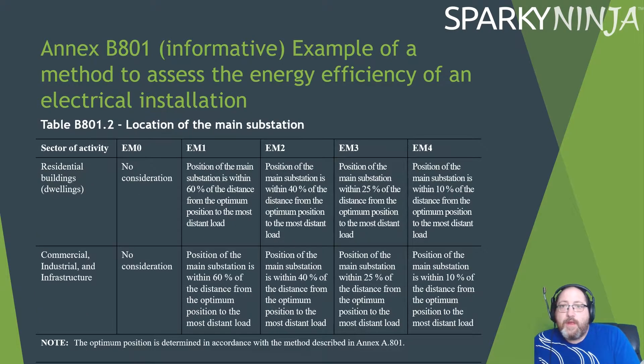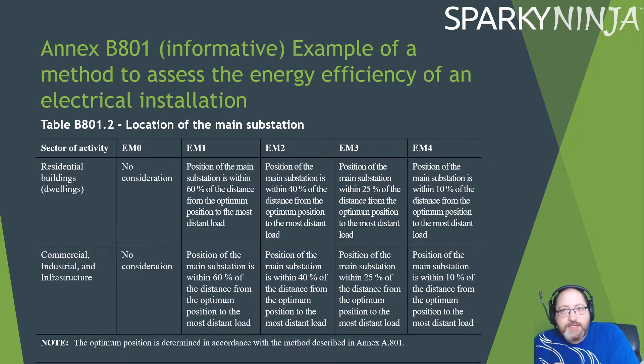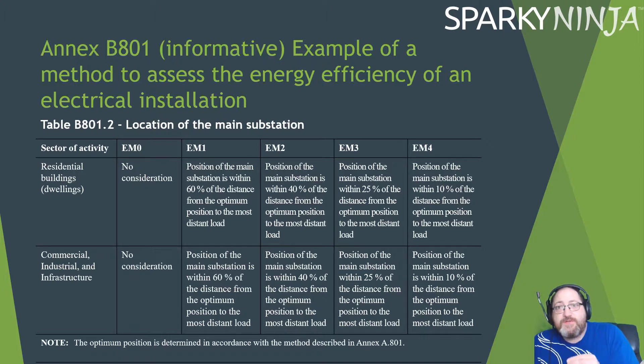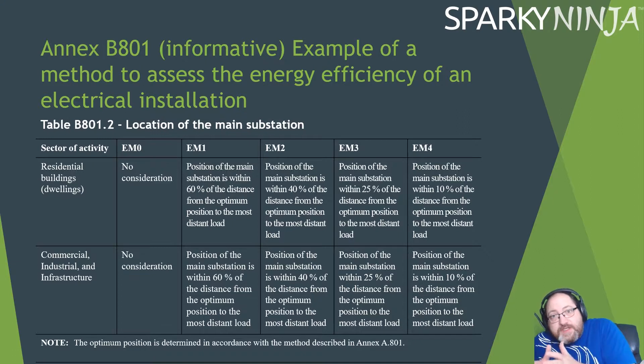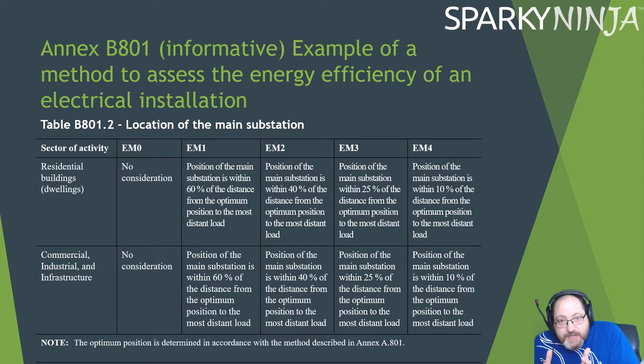For location of the main substation — having done the barycentre method calculation — if there's no consideration, you get zero. If you position the main substation within 60% of the distance from the optimal position to the most distant load, you get a one. The closer the substation is to the optimum position relative to the most distant load, the higher your score.